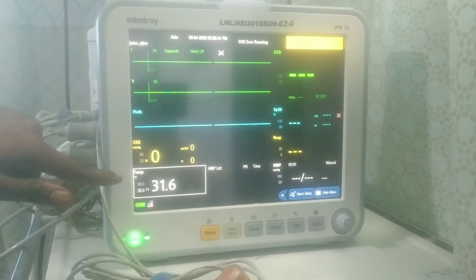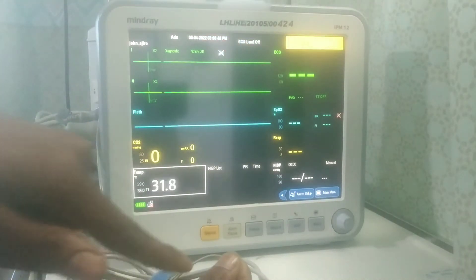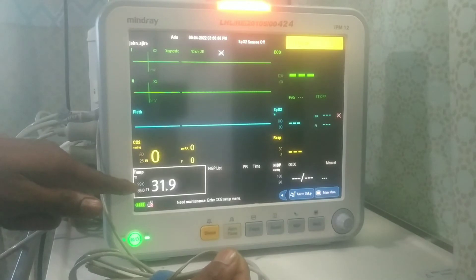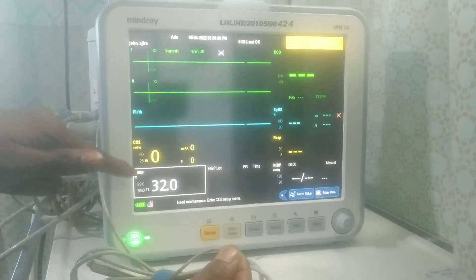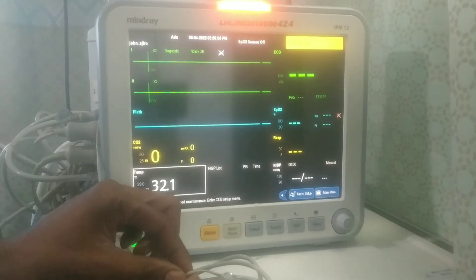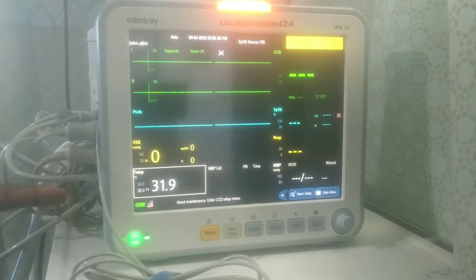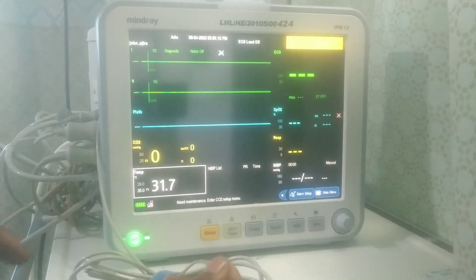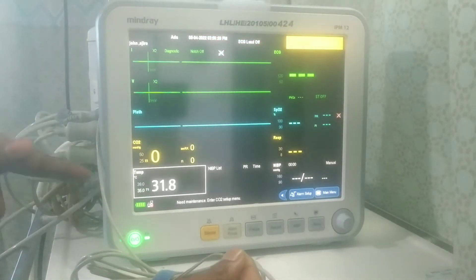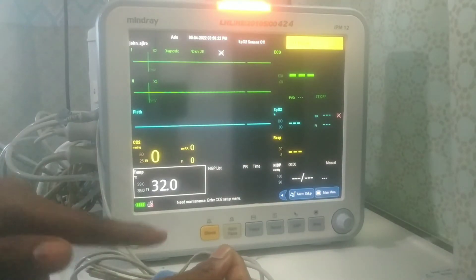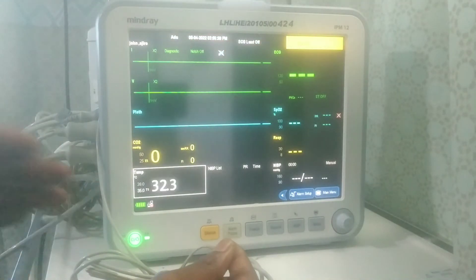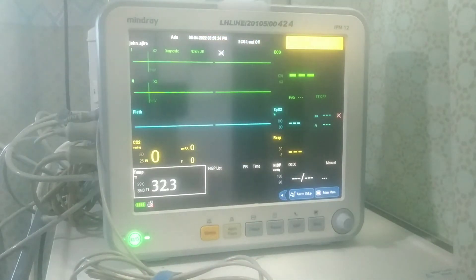The reading is now going up — that means it is reading the temperature of the body part attached to the probe. When I take my hand off the probe, you will see it decreasing again. And if I hold it again, it starts increasing again. This is the part you attach to the patient in order to get your temperature reading from the patient's body.